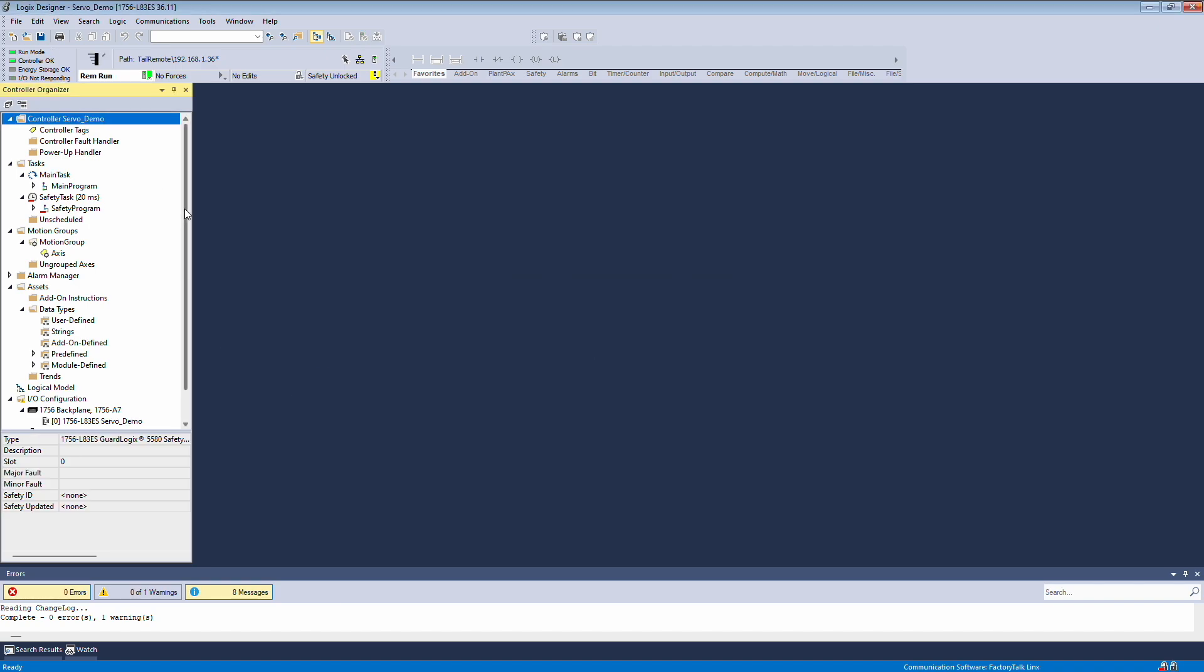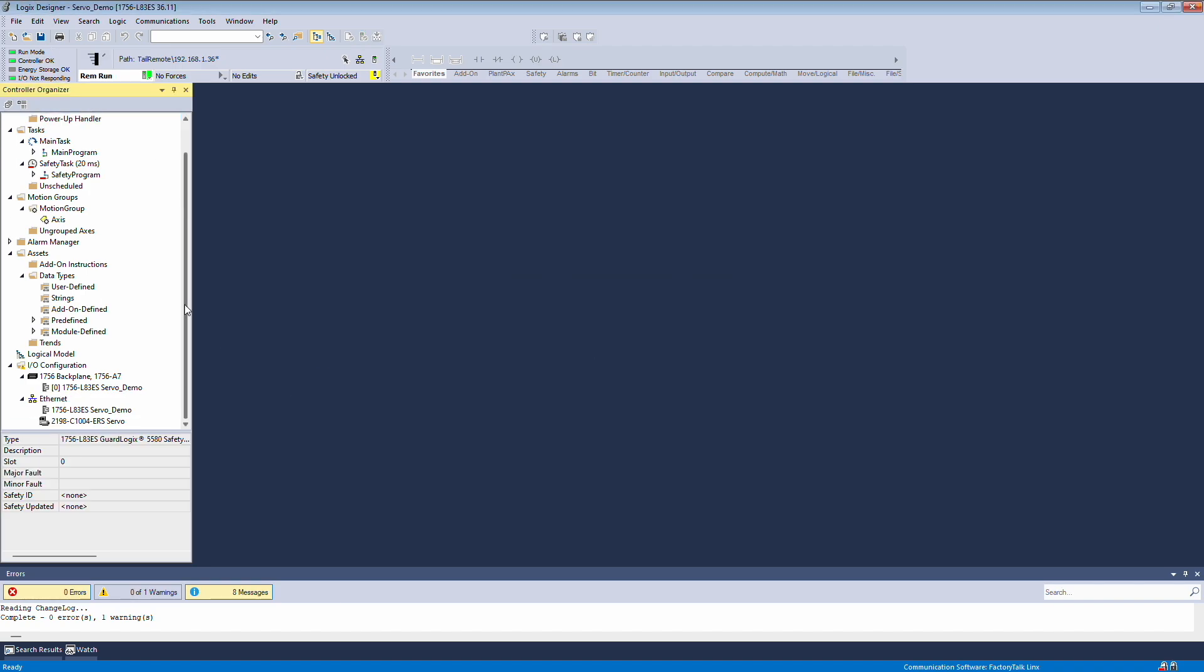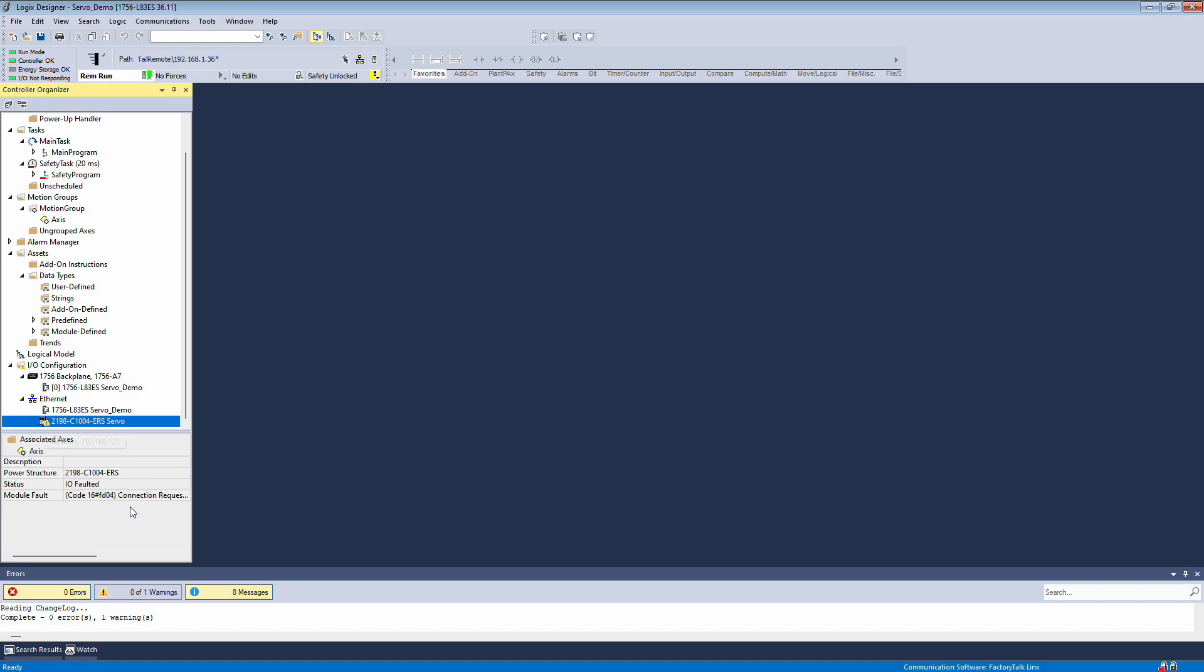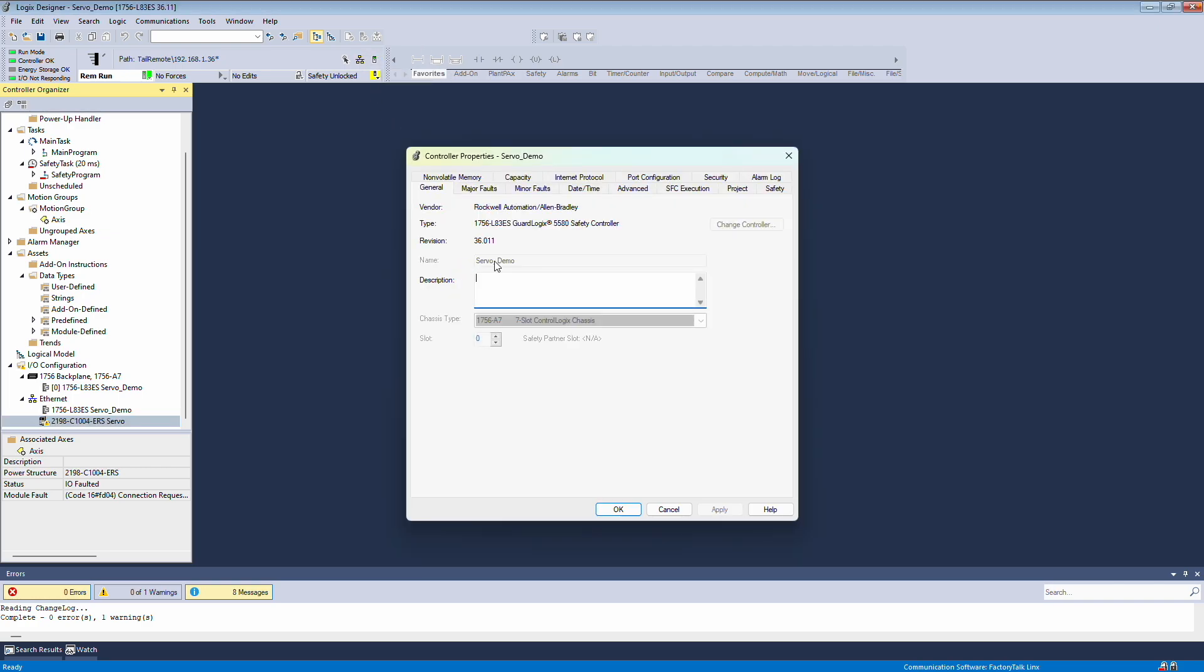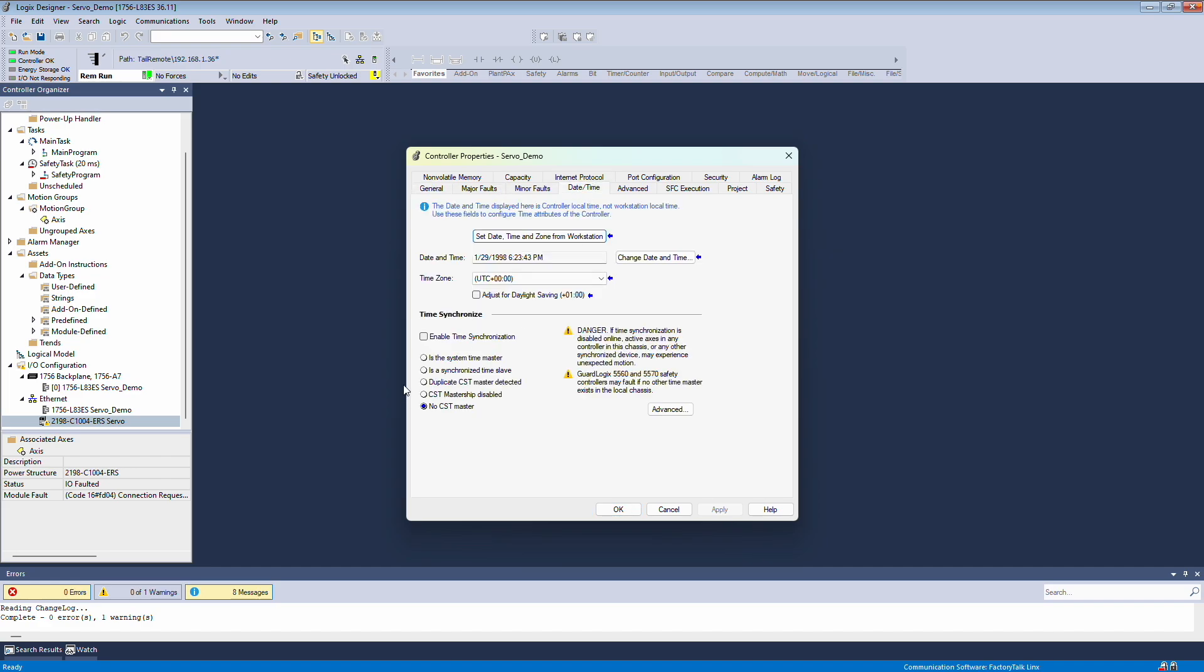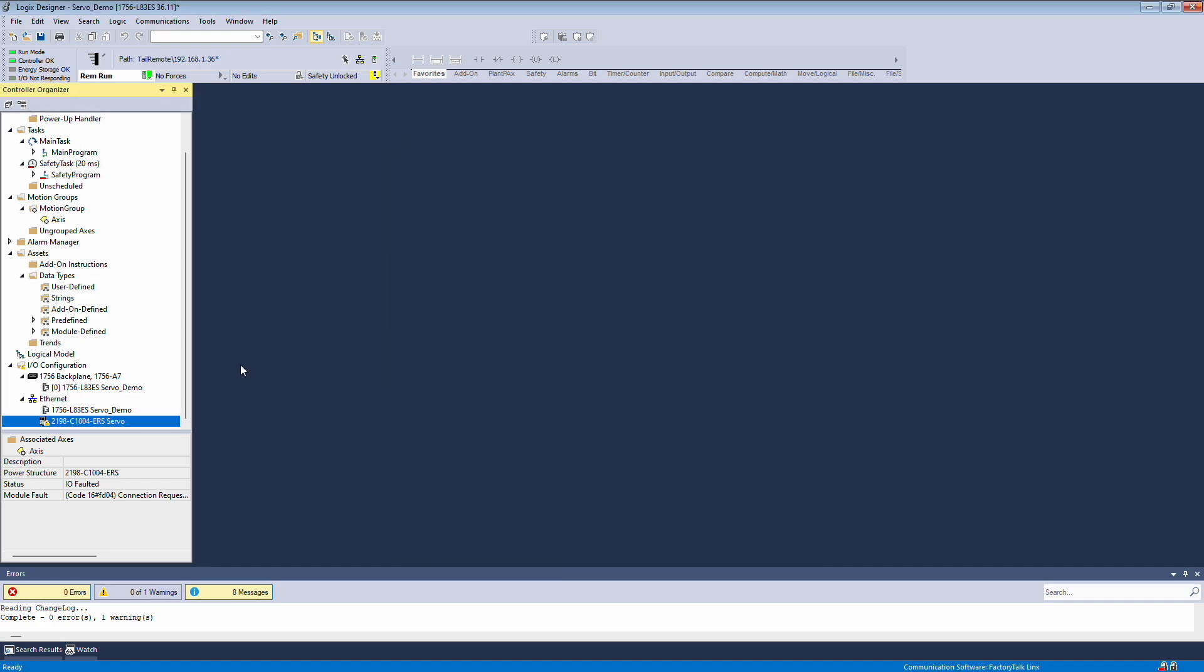The first thing you might notice is an IO not responding message. If you check the error message, it indicates that there is no CST master detected. To fix this, we need to ensure that time synchronization is enabled as servo drives require a time synchronization master. In this case, we'll make the PLC the time master. This is done under Date and Time by checking the box to enable time synchronization. That should resolve the error.